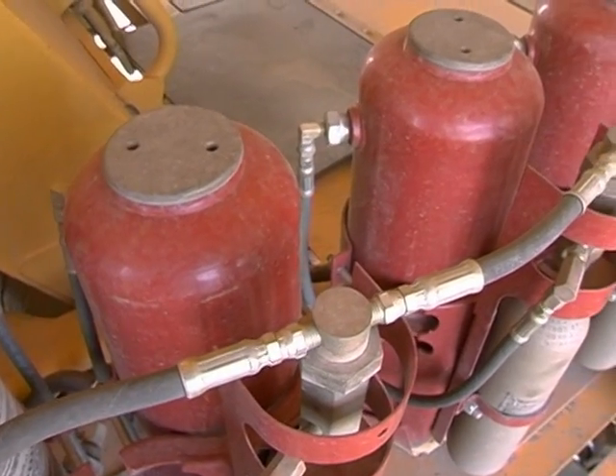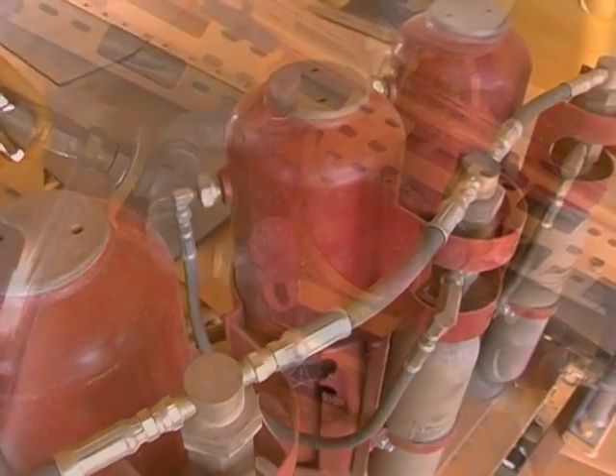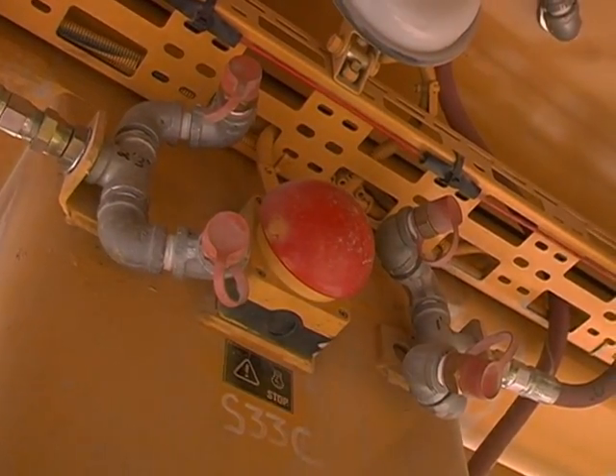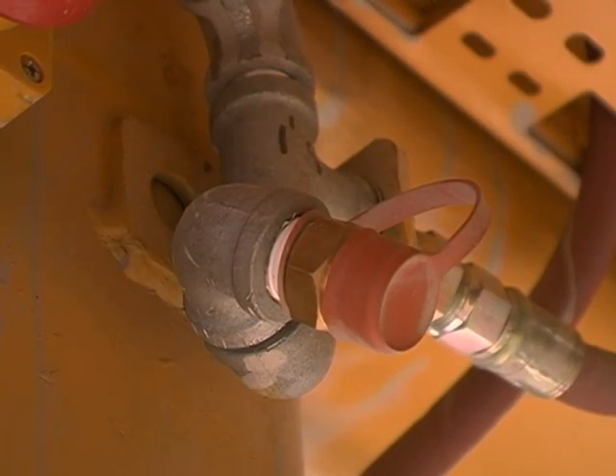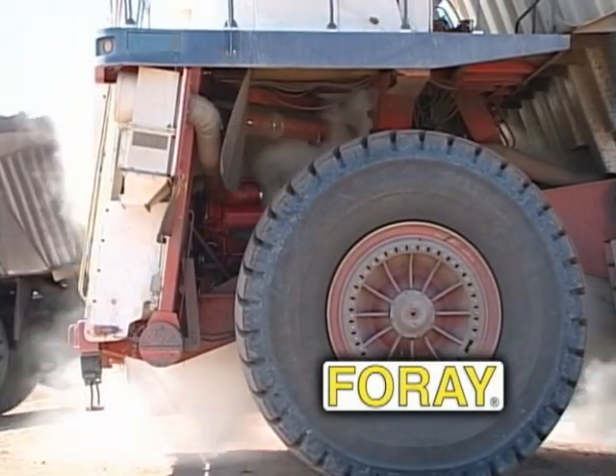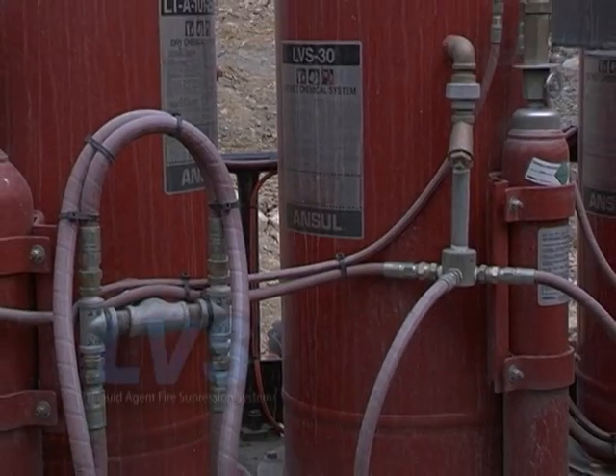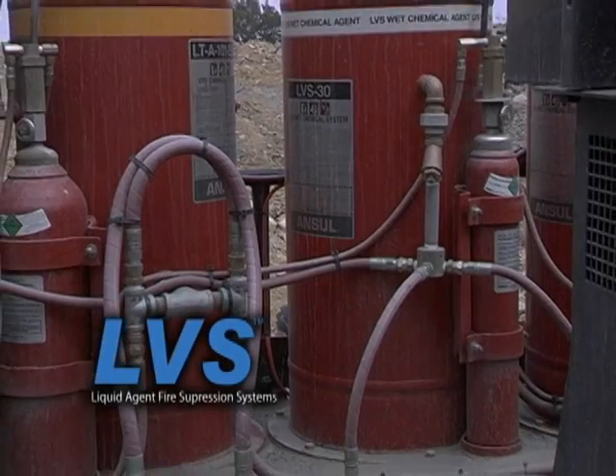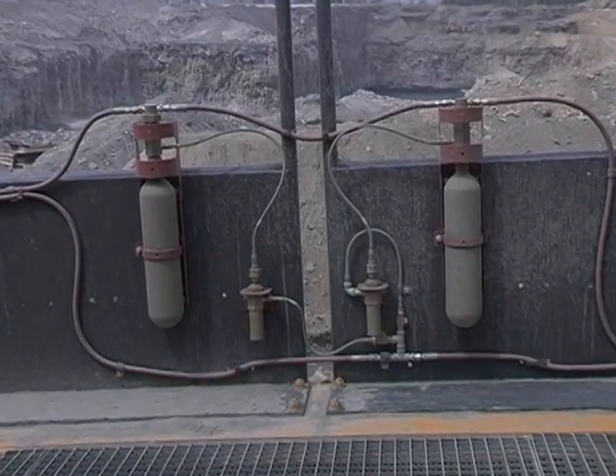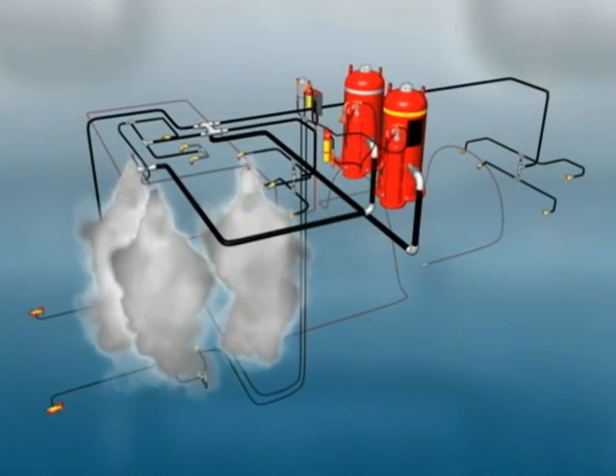Manufactured for dependability, the corrosion-resistant systems are designed for temperatures from -65 to 210 degrees Fahrenheit. The 4A dry chemical extinguishing agent acts quickly to control and suppress the flames. The LVS liquid agent, stored in 15 or 30-gallon tanks with nitrogen cartridge supply, is deployed, effectively cooling down the hazard area and helping to prevent fire reflash. The response is rapid, with a phenomenal LVS cooldown rate of approximately 6 times faster than dry chemical.